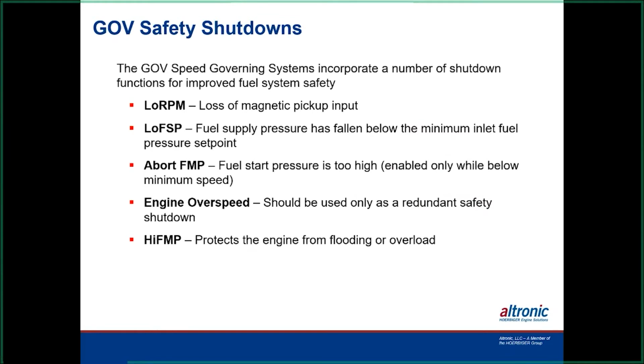These are some of the shutdown functions that come with it: low RPM, low fuel supply pressure, abort on the fuel manifold pressure, engine overspeed, and high fuel manifold pressure. These are all things that need to be programmed into the valve for safety purposes, for shutdown, and make sure that the valve doesn't get out of control. And these will all come up on your keypad there if anything does go wrong.